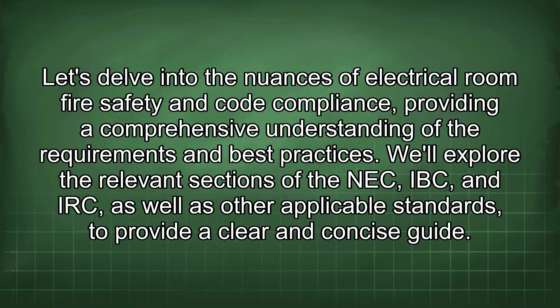Firstly, let's examine the NEC stance on fire-rated doors and walls for electrical rooms. While the NEC focuses primarily on electrical safety, it does not explicitly mandate fire-rated doors or walls for these spaces. However, the NEC does address other aspects of electrical room safety, such as working space requirements, equipment clearances, and ventilation. These requirements are designed to minimize the risk of electrical hazards and ensure the safety of personnel working in or around electrical equipment.